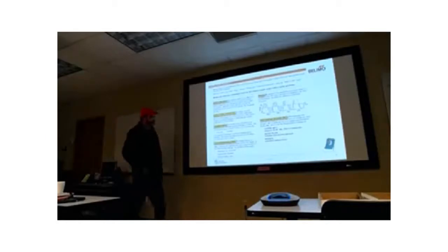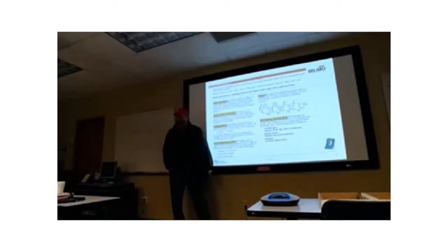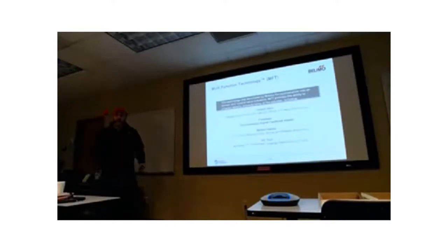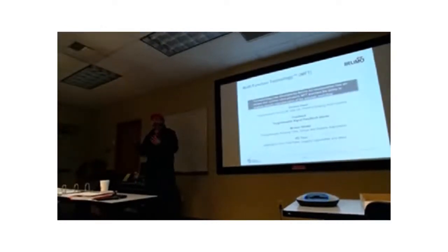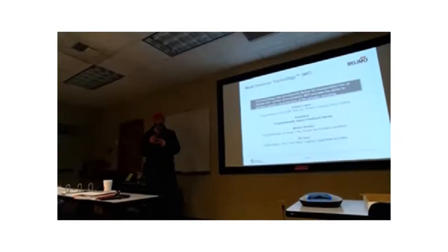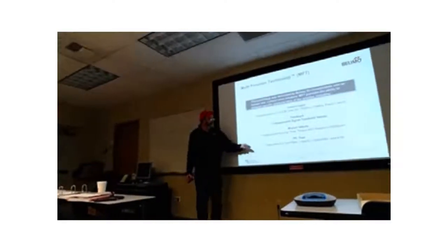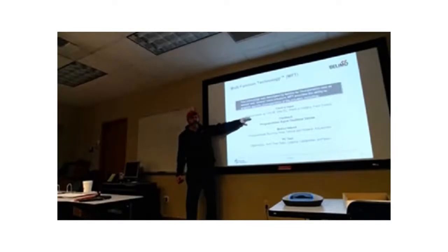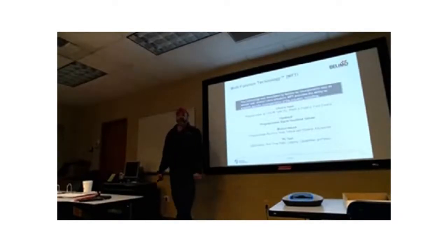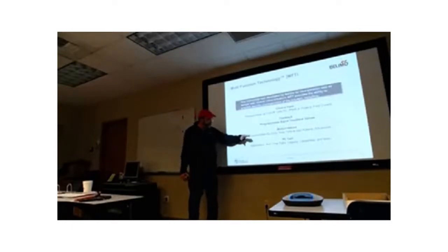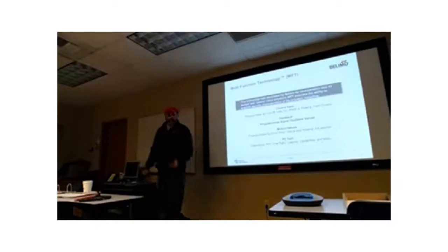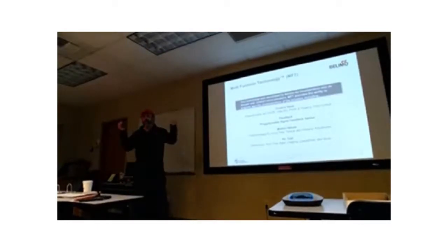And then MFT, or multifunction technology, this is more of a technology. It's not really a control signal. I'll give you a mechanical engineer's definition: it's a fancy motor controlled by a chip. That chip can be programmed to make this actuator an on-off actuator, a pulse width modulation actuator, a floating point actuator, or a proportionally controlled actuator. You can change the runtime, the torque, the angle of rotation. You just program it, and it changes the rotation.